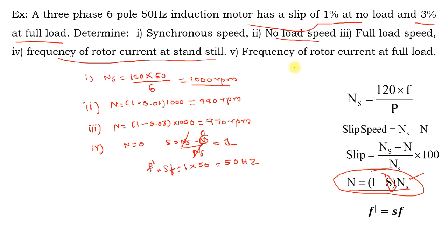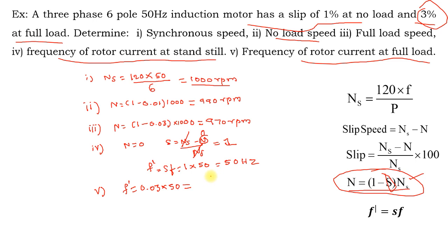Finally, rotor frequency at full load: full-load slip is 3%, so s = 0.03. Rotor frequency f' = 0.03 × 50 = 1.5 Hz.